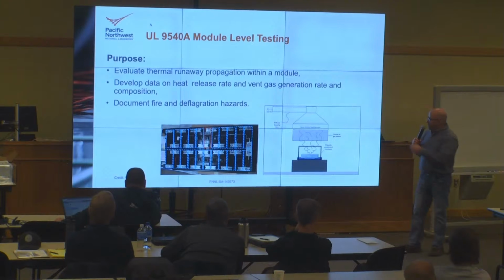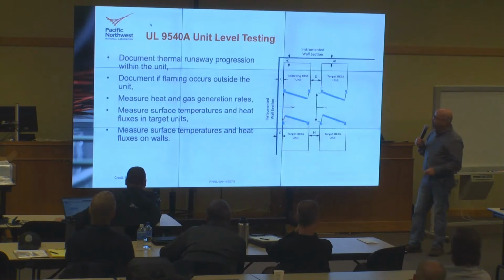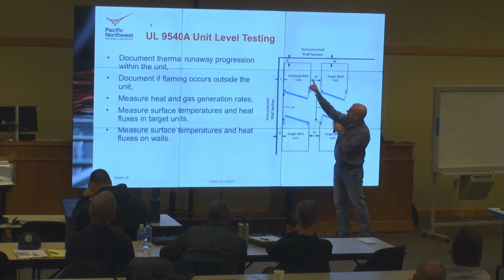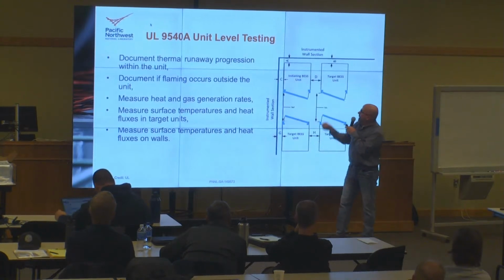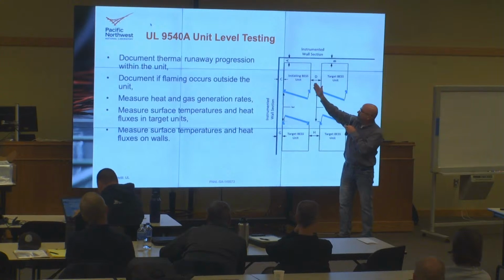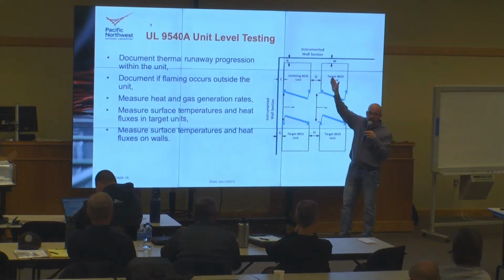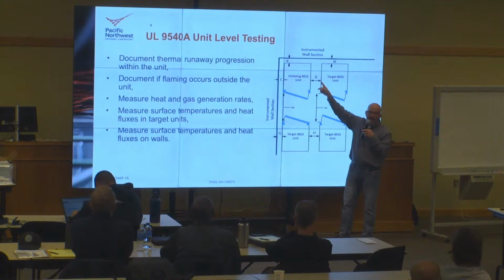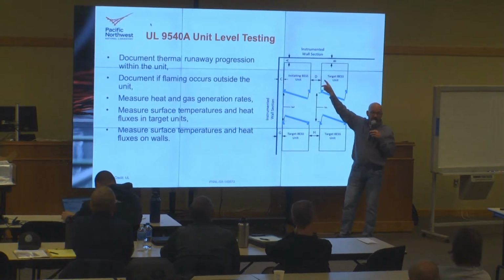And we also want to know what deflagration hazards there are. Here's the unit level test. So the initiating unit, we want to know what's the temperature on this unit, what's the temperature on the walls, and that will help inform, can you have it right next to it, or does it need to be further away? And you can't be more than 97 degrees above ambient, Celsius, above ambient.